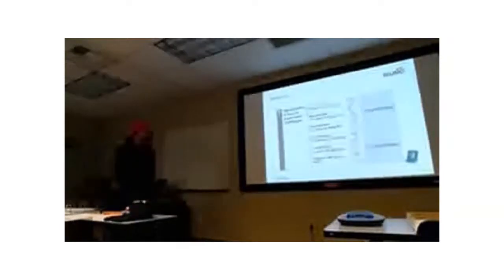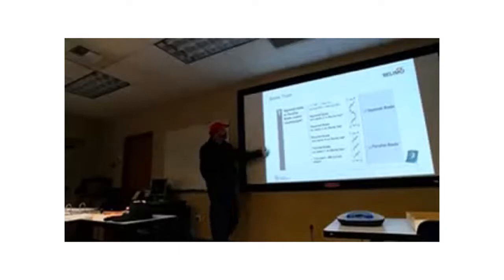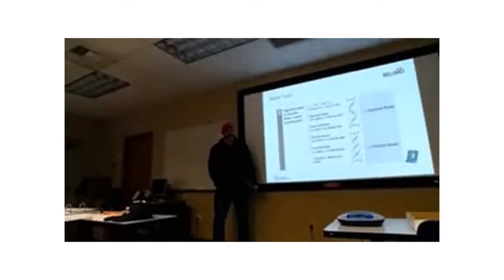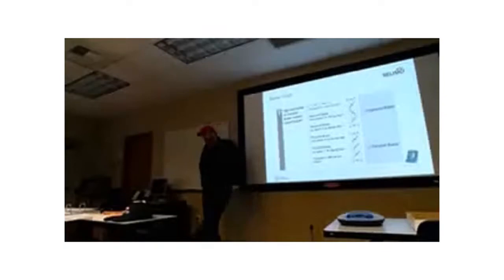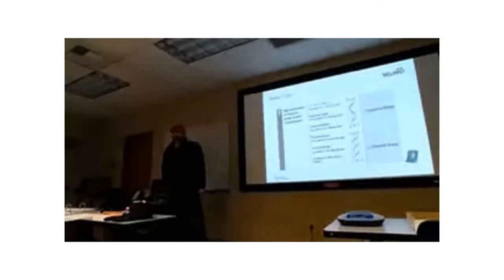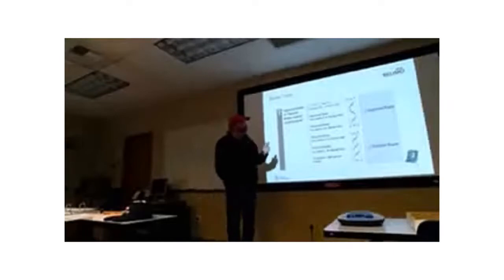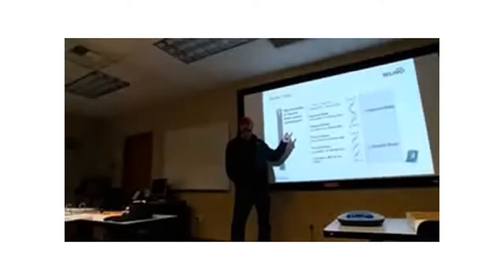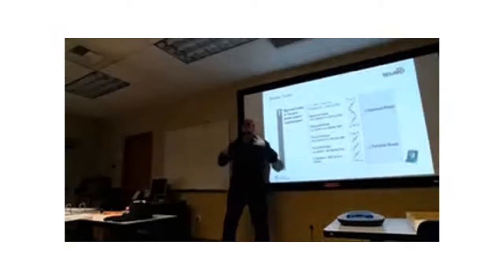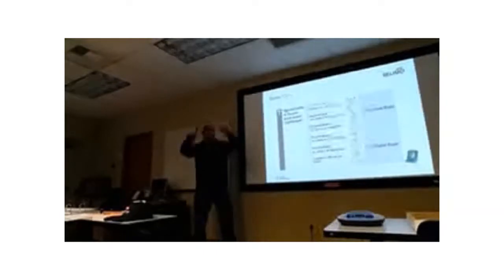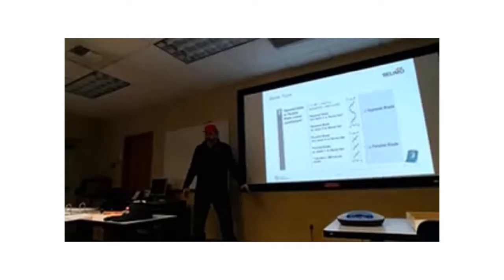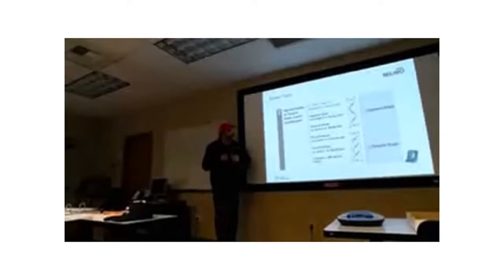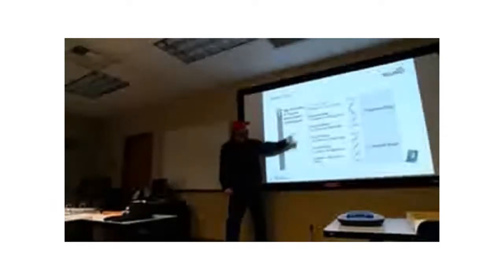So there are two different types of dampers in HVAC. We use what we call opposed blade dampers or parallel blade dampers. Opposed blade dampers, if you've been in the field, you'll typically see them. Well, maybe I'll ask you, where do you see them? Outside air, okay. Yeah, outside air would have an opposed blade. Typically, relief air might have an opposed blade. Anytime you want to control the throttling of the air, we call it throttling, right? We want to control that to a certain value. The registers in your house, right? If you have a heating system, those are opposed blade. So anytime you want to throttle the air and control it to a certain value, you use opposed blade.